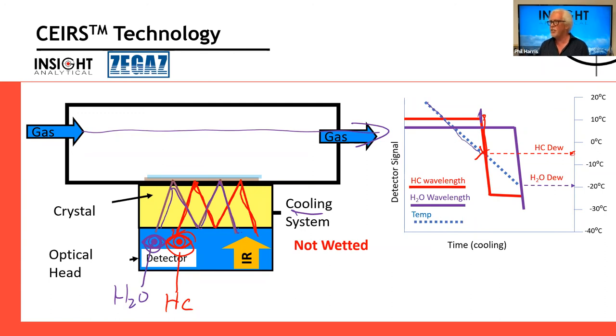So now the analyzer says, okay, I've just found both dew points. I'm going to stop cooling and let the crystal warm back up. All the stuff that condensed on the surface evaporates away. And now I'm ready to go again. So the measuring process is: cool the crystal, watch both wavelengths. When the hydrocarbon wavelength gets hit, we know you just hit a hydrocarbon dew point. When the water wavelength gets hit, we know you just hit a water dew point.